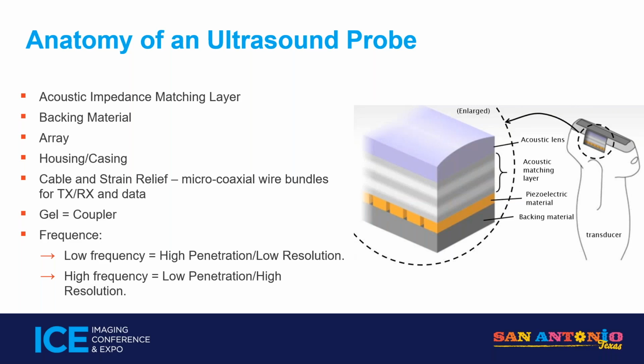Backing material, again, I don't really worry about this stuff. The array, we can tell you that your array is broken if you send it in for evaluation, right? We can evaluate the array. It's pretty obvious. If you see that the array has a dent in it, it probably got dropped or slammed against something, and it's glass. I mean, think of the material as being glass. It doesn't take a lot to crush it, okay? Housing or casing should be not cracked, not damaged, not separated. So if you see any of that, you should get it in and get it repaired.